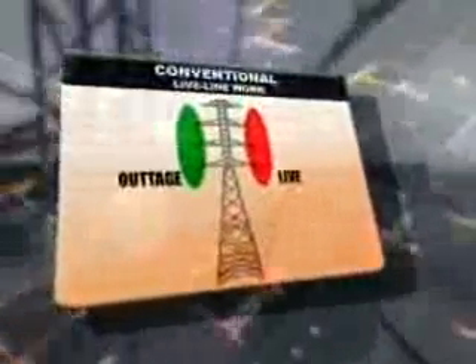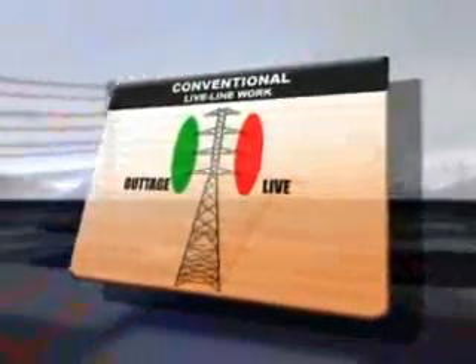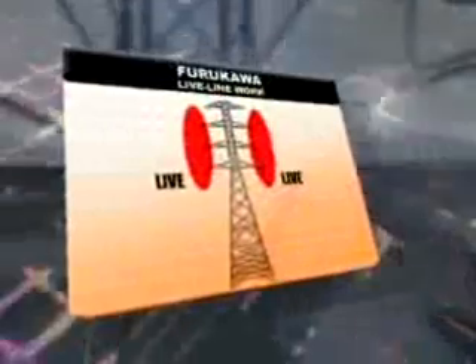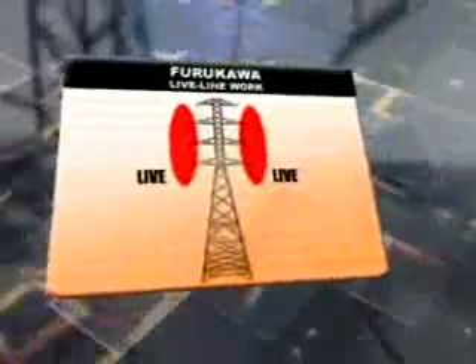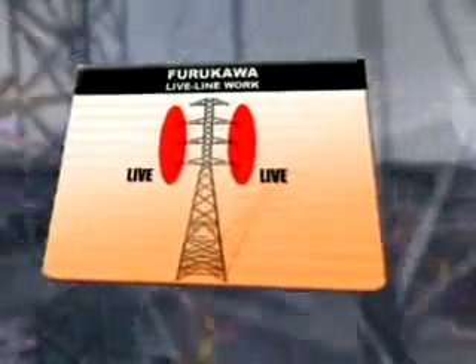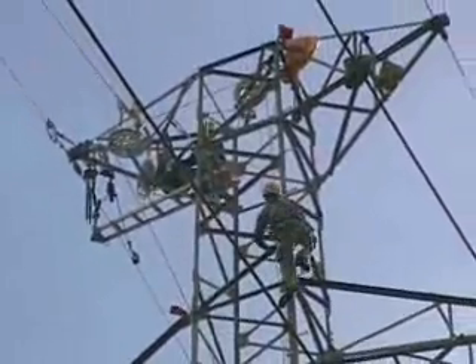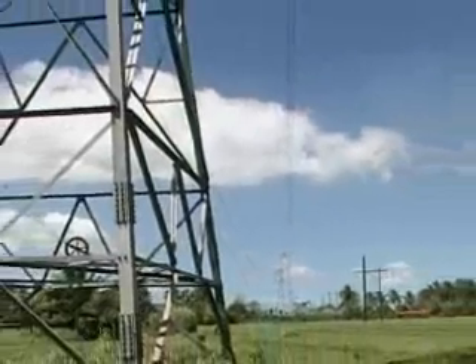To replace the existing grounding system with OPGW in a conventional OPGW live line installation method requires an outage or power shutdown to the affected area, which adversely affects consumers, including power suppliers, in terms of revenue and convenience. However, in Furukawa's new technology, OPGW installation can be done in a live line condition on both circuit without jeopardizing the safety of the crew, as well as the existing power transmission line. Therefore, this method guarantees uninterrupted power supply.